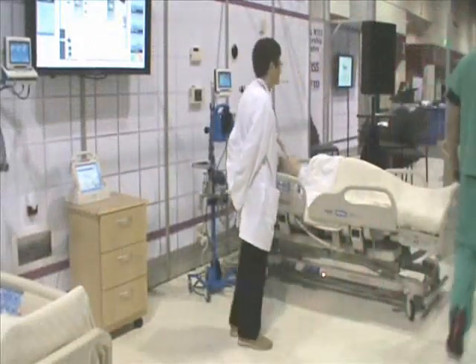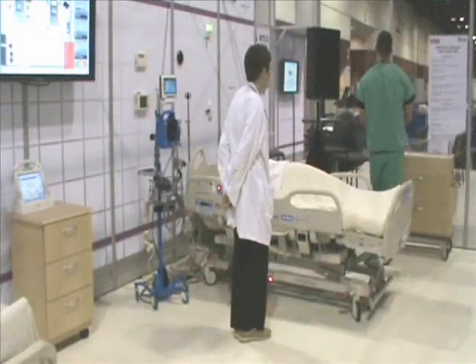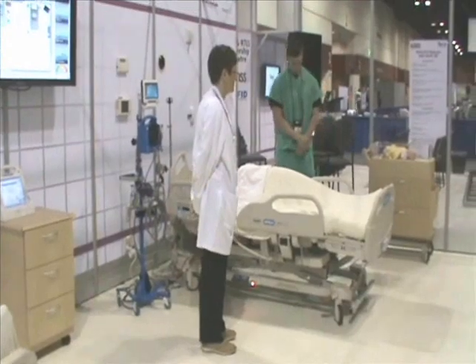Because I was responding to this emergency scenario, a potential opportunity for infant abduction became available. Should there be an unauthorized attempt to remove the infant, an alarm will sound notifying the staff. In some situations, this may be integrated with door locking mechanisms and elevator controls in order to limit access to egress points. The system controllers may be programmed so that when an authorized member of the staff escorts the infant through the exit, no alarm is generated. These types of association and exit alarms are vital for infant protection. They can also be used to prevent dementia patient elopement and to mitigate asset shrinkage.